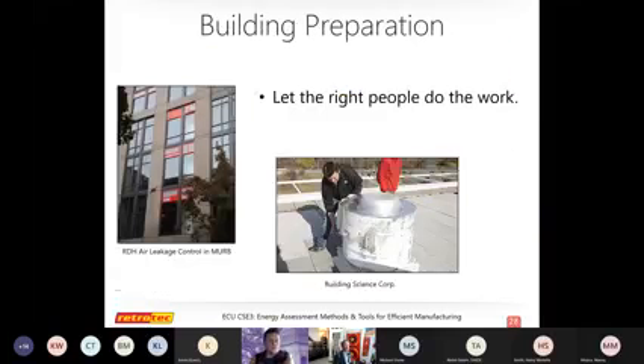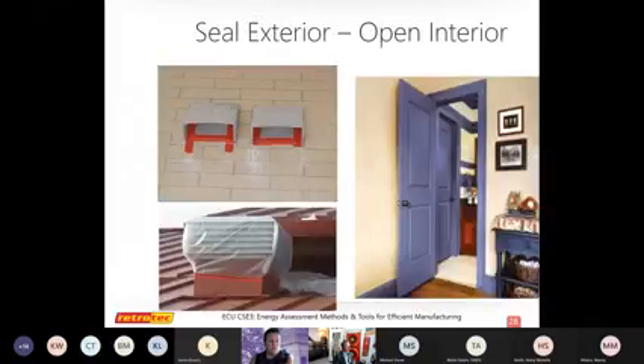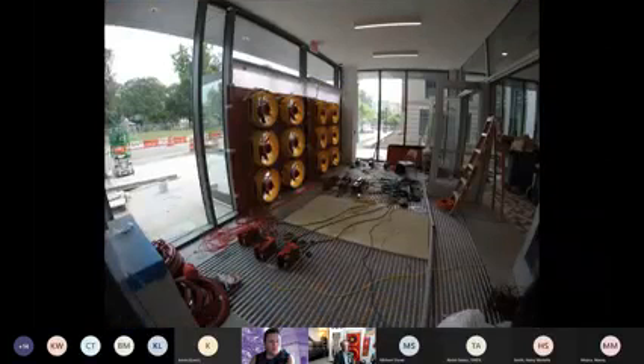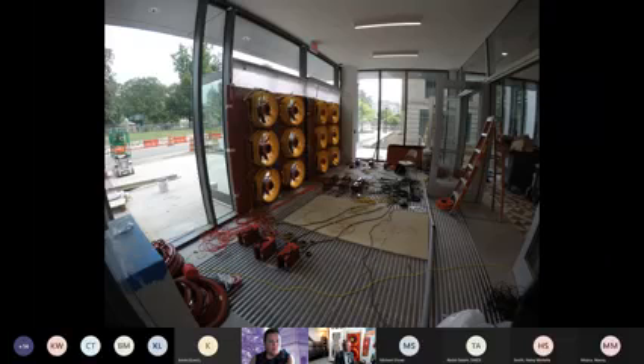And there's a little bit of prep work involved too if you're going to have one of these tests. Sealing up exhaust fans, any leakage that we don't want to count. Depending on how big the building is depends on how complex the test is going to be. We want all interior doors opened up and all mechanical fans turned off and things like that. So that's why a lot of these tests happen at night for manufacturing facilities. And as we get the test set up, that's what it looks like. The number of fans, again, just depends on the building.